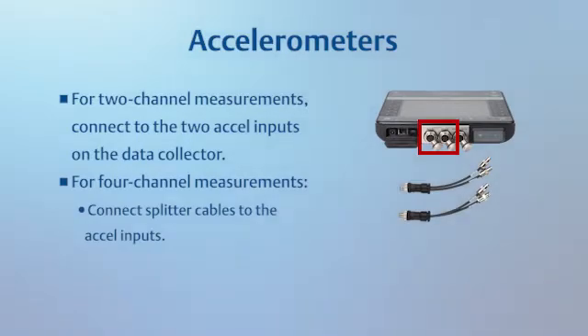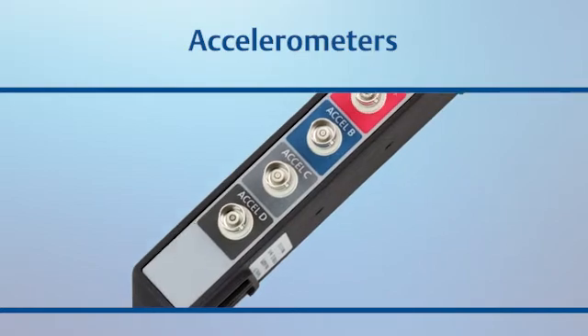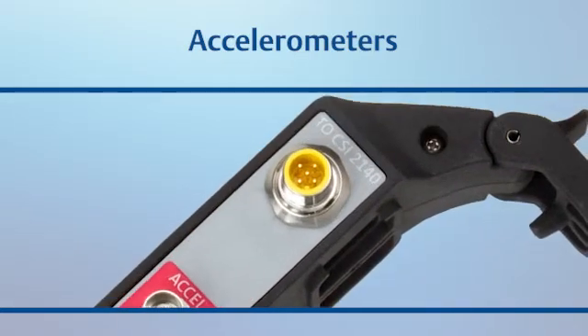On the AMS 2140, there are three ways to connect your accelerometers. If you are collecting only two channels of data, you can connect directly to the two accel inputs on the collector. If you are collecting four channels of data, you have two options: you can connect splitter cables to the accel inputs, or you can use your four-channel adapter. This adapter works with both accelerometers and displacement probes, so be sure you are connecting to the side where connectors are labeled Excel. This side has only four connectors, plus one connection to the collector.